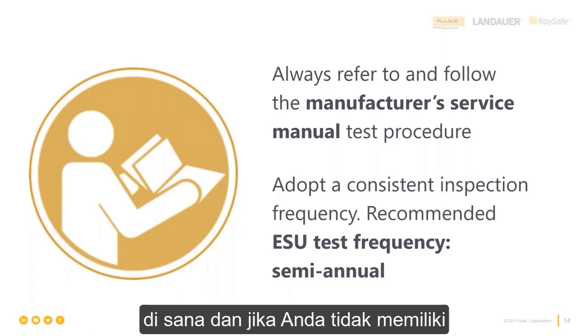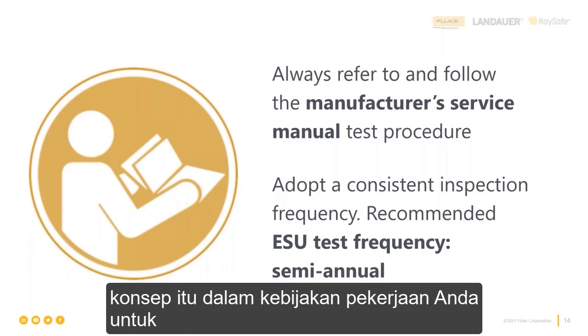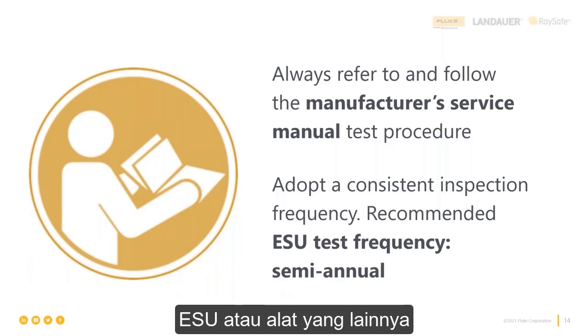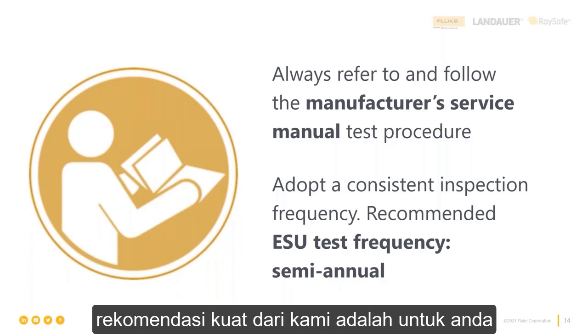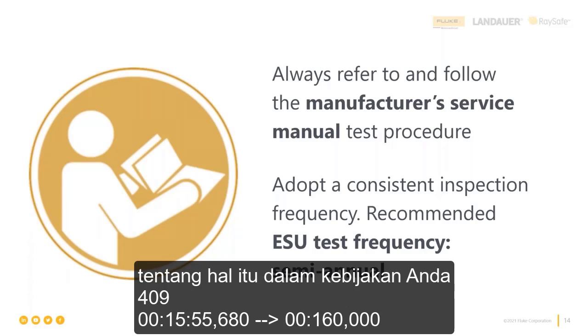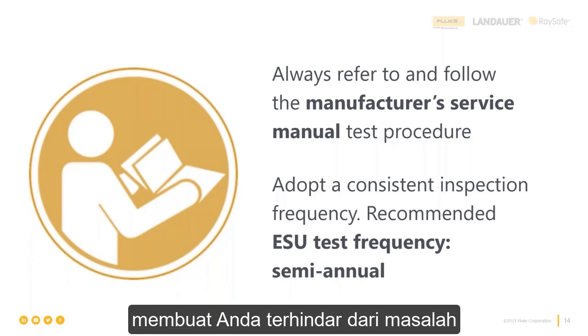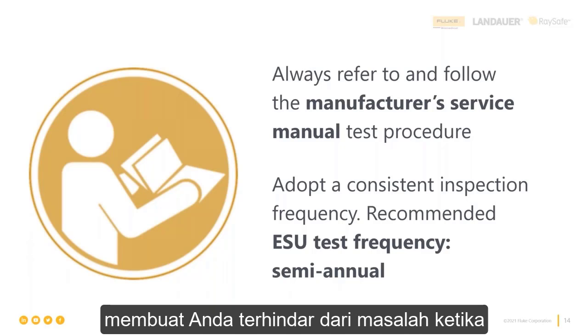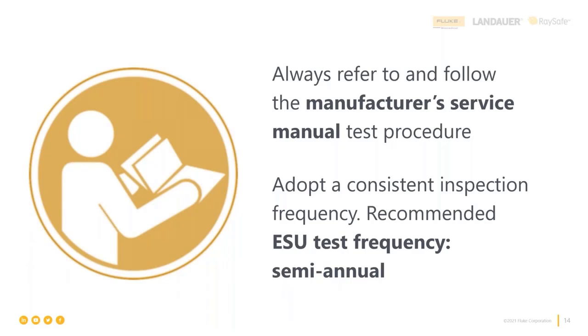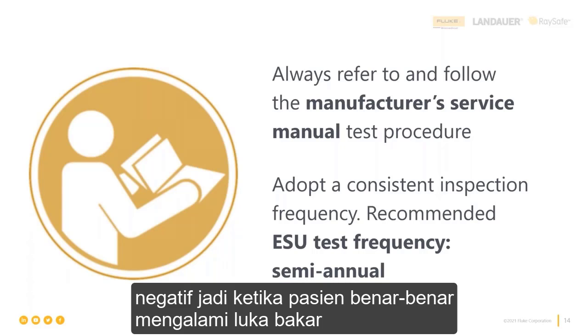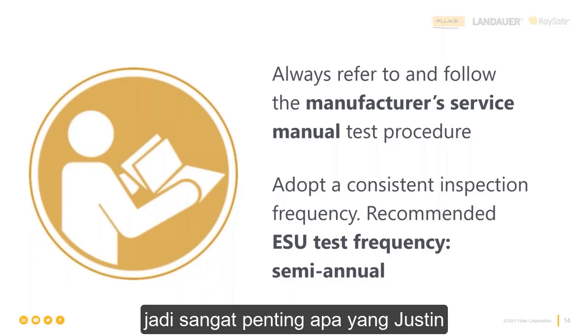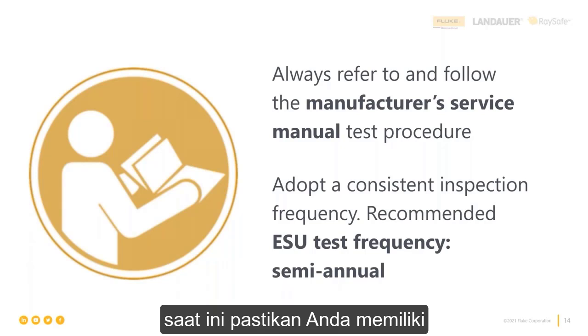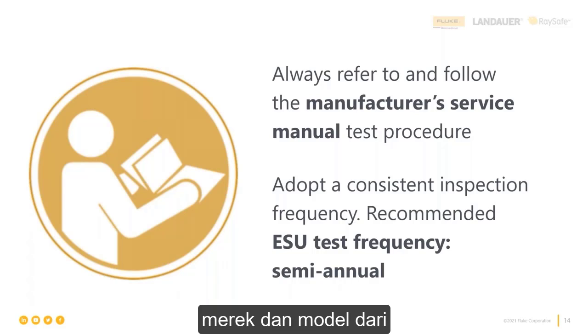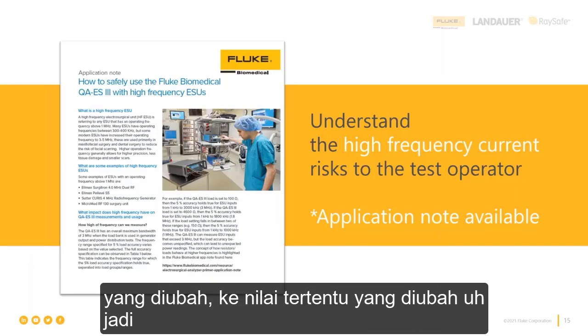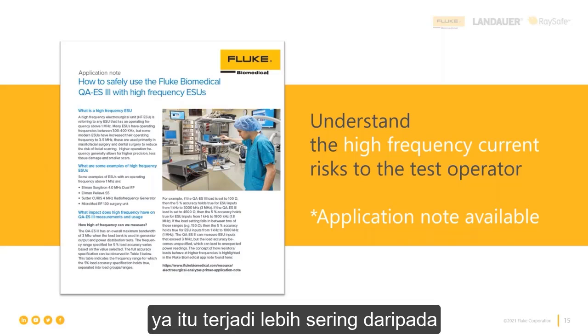So yeah, Justin's making a really good point there. And if you don't have that work assignment, or you don't have that concept in your policy for medical device quality assurance, whether it's ESUs or anything else, our strong recommendation is you add it and you adopt it and you talk about it in your policy as what you say you're going to do, and then make sure you do it, because that'll keep you out of trouble when it comes to audit trail, but it'll also keep you out of trouble when it comes to litigation about negative incidents. So where a patient actually got a burn or something like that. So it's really important what Justin is saying about keeping current. Make sure you have the latest version, brand by brand and model by model of medical device, and especially ESUs. Yeah, we've seen everything from steps changed to certain values changed. So yeah, it happens more frequently than some people are aware of.